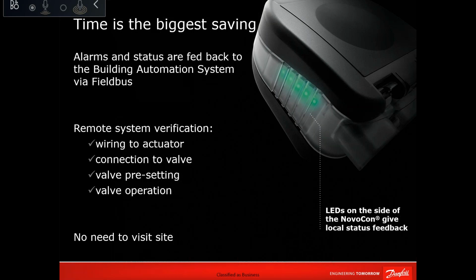Okay, next question. Can we set design delta P on Novocon? Delta P. Maybe in the future, we are trying to find a differential pressure sensor small enough to be built in or to link with Novocon. Our R&D are working on it, but you cannot set minimum differential pressure. But if you already have sensors installed, and the output of that sensor is 0 to 10 volt, then you can use that to control anything. And the information can be transmitted through the Novocon to your BMS. But measuring delta P from the Novocon itself is not yet available.